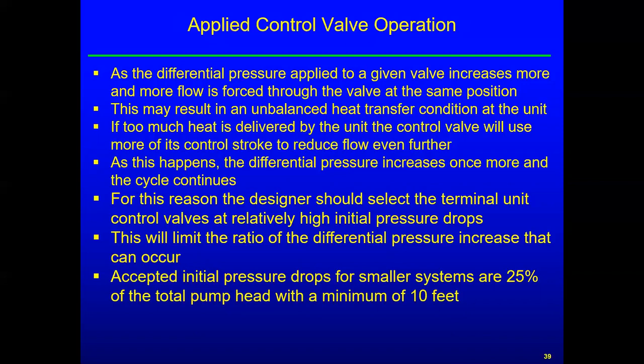Now, what happens in the system, and we'll see, is if we have a bunch of these control valves, as some of them start shutting, that's going to up the pressure in the distribution piping, and that can then force more flow through a different coil than the one that, say, its control valve didn't change, but its neighbors changed, which upped the pressure, which then forces more water through that one. And so that causes an upset in the system because you get more heat delivered to the space when you really weren't calling for it. So as this happens, differential pressure increases once more. So then that room's valve starts to shut because it starts overheating. That ups the pressure again, and this cascades through the system.